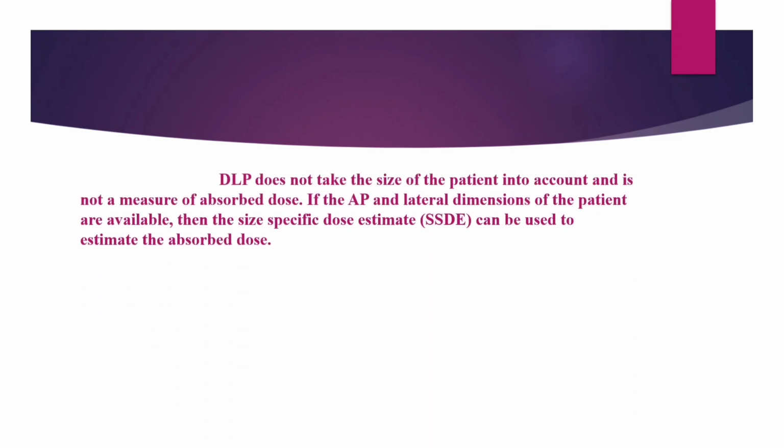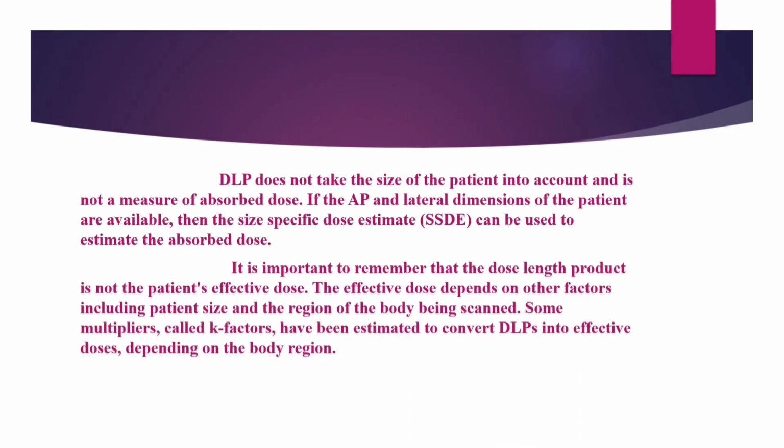Dose length product does not take the size of the patient into account, and it is not a measure of absorbed dose. If the AP and lateral dimensions of the patient are available, then the size specific dose estimate can be used to estimate the absorbed dose. It is important to remember that the dose length product is not the patient's effective dose.